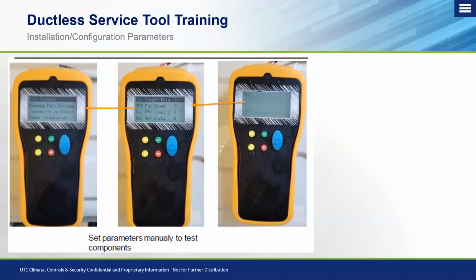This is how we go in and individually fire off the compressor, the fan, the EXVs, and the 4-way valve. And this is the menu that we're going to get into to manually adjust those individual components in the outdoor unit if we suspect them of being bad and we want to test them.